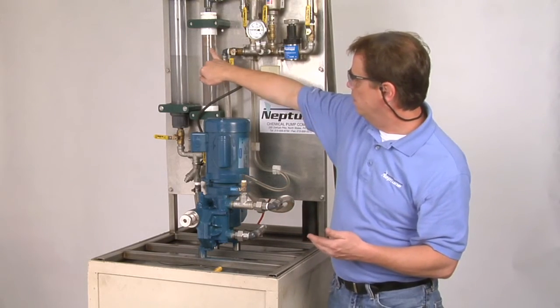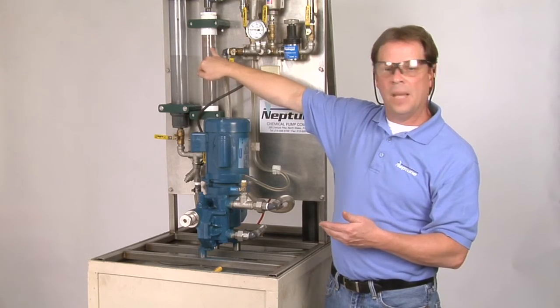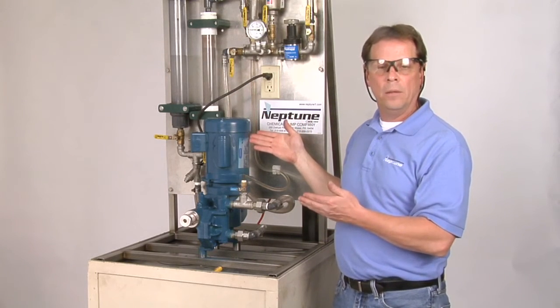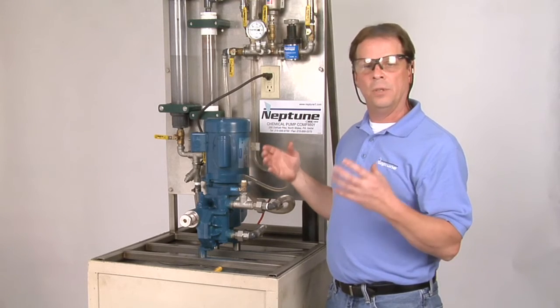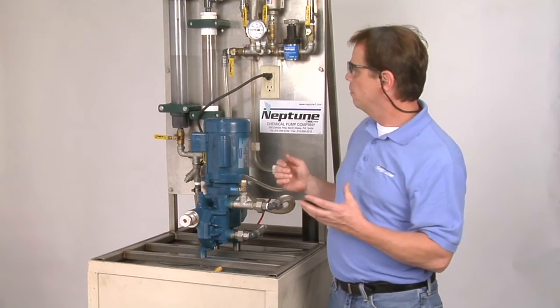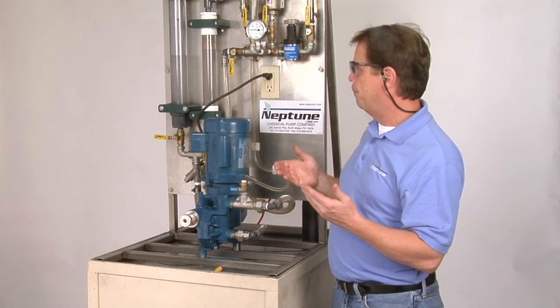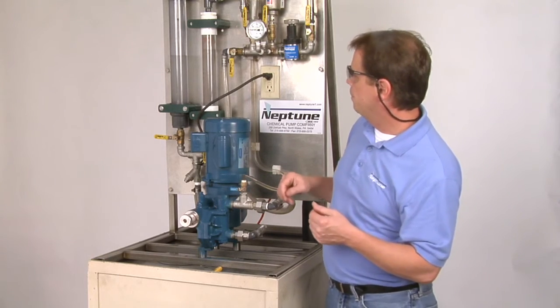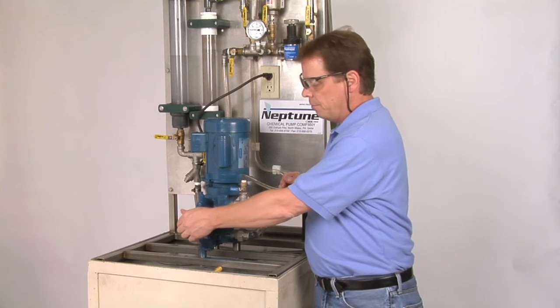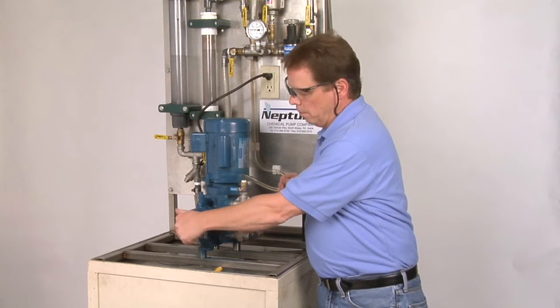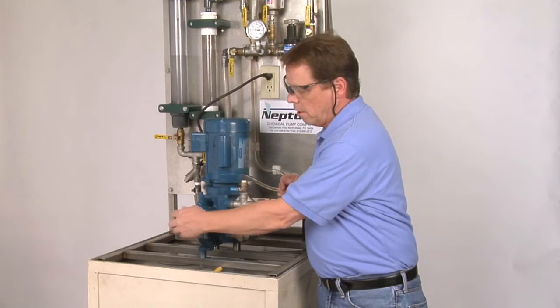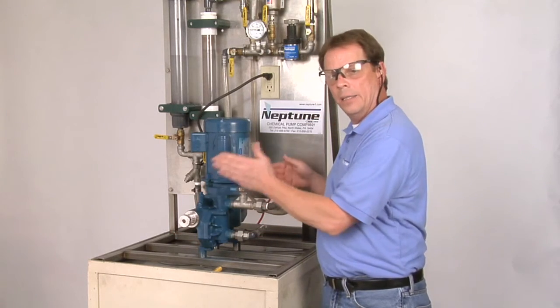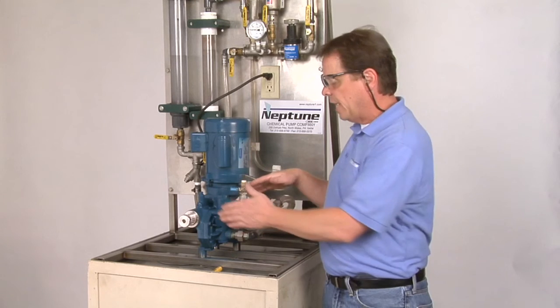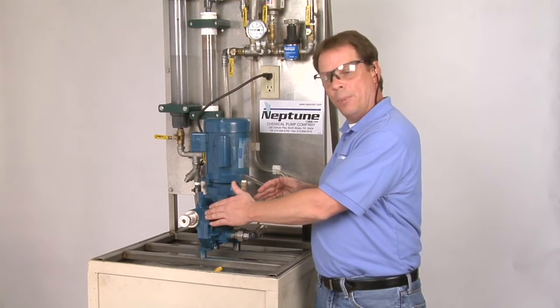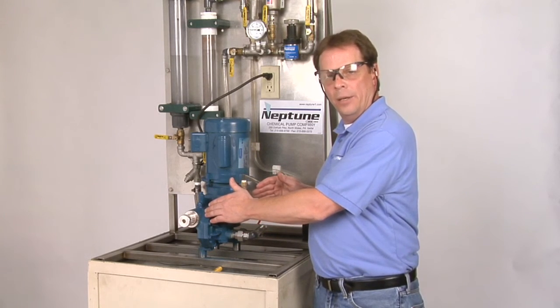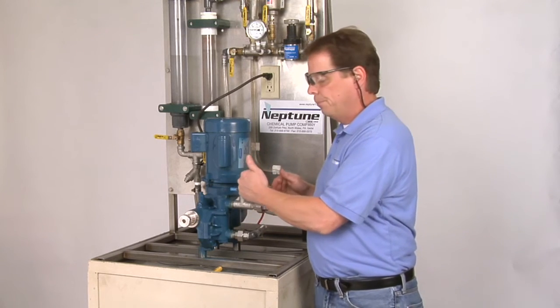And as you see, we are starting to pump. Now this pump has already been broken in, but typically if you have a pump that's relatively quick or faster, it will start to pump. Now after that 5 minutes, we'll take it down to 0. All we're doing is just getting that oil hot and getting it moving. And if there is any air back behind that diaphragm, even though we purged it, sometimes there could be air behind there still. We can cycle it through.